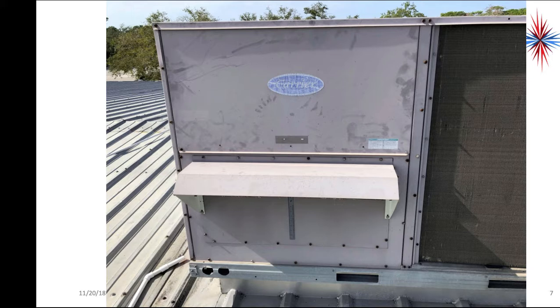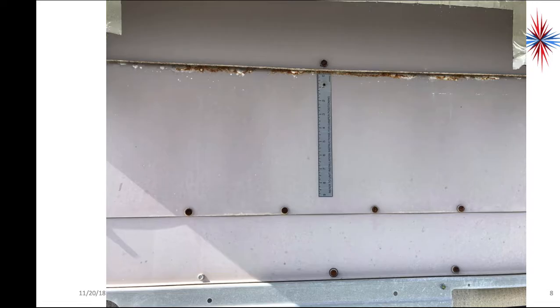Start taking a look at the rest of the unit. We want to take a look at the economizer, which is this area right here. Economizer, if you remember, is the part that actually pulls fresh air into a building. And we look at the economizer, and that is totally shut. In fact, on the outline of the picture here, you can see that someone actually taped it shut, so it wasn't operational anymore.